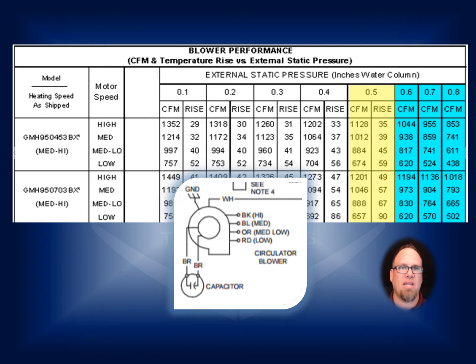They equal 0.8. And if you look at our example here on this GMH 95, if we had 0.8 inches of static and we were on high speed with this air conditioning system, we'd have 853 CFM. Now, is that the right amount? I don't know. It depends on what size the condensing unit is. Is it a 2-ton unit? Is it a 3-ton unit? Is it a 5-ton unit? Those are what make the difference.